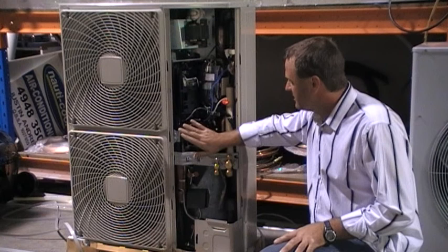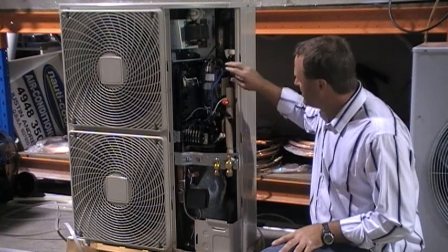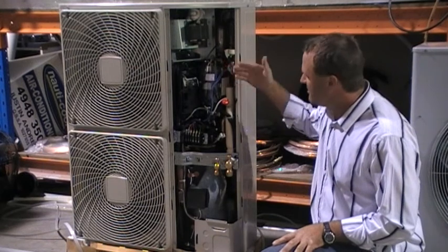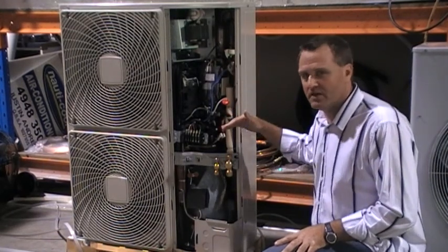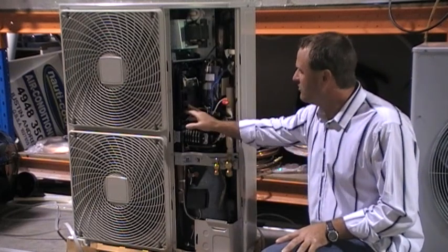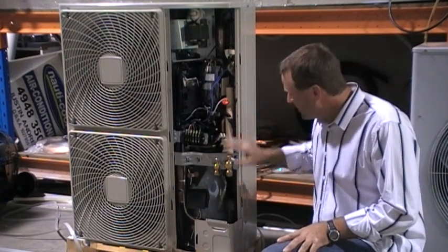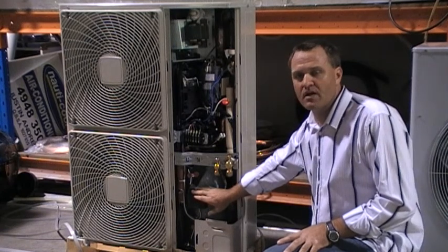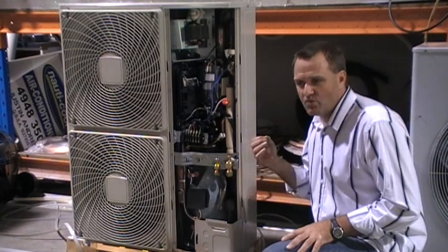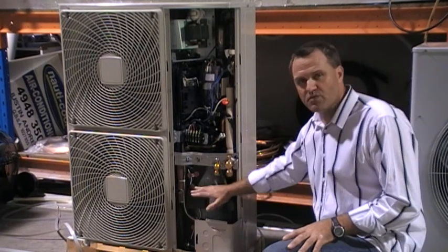What happens is 240 volts power comes into the unit. The power gets cleaned up through the noise filter boards, then gets turned into DC power through the power board, then back through to AC 3-phase, and then our control board will actually alter the frequency that 3-phase power comes out, which will make this compressor speed up and slow down. The idea behind an inverter is that it will run flat out to get the room down to temperature. Then when the room is at temperature, the compressor will actually slow down.